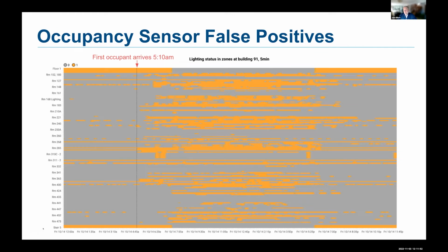I mentioned occupancy sensors. You've all dealt with occupancy sensors for decades now, originally installed for lighting control systems. Over the years, occupancy sensors often have digital outputs. Over the years, we've had cases where we try to use those for mechanical system scheduling as well. And the more we've gotten into looking at occupancy sensors, we see a lot of issues and a lot of false positives in this case. Generally, it's quite a challenge to stay on top and get all those occupancy sensors working.